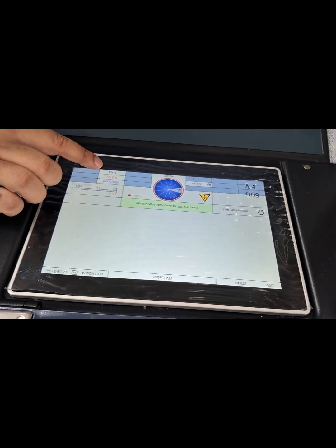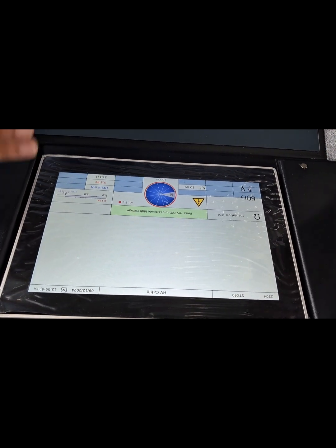High voltage. Only 3.3 kV is going. And you can see that resistance values are some ohms to kilo ohms, in between. You can say it is decreasing now. So it is a kind of short circuit. Not a perfect test. Stop. Yeah, you can say stop, no problem.